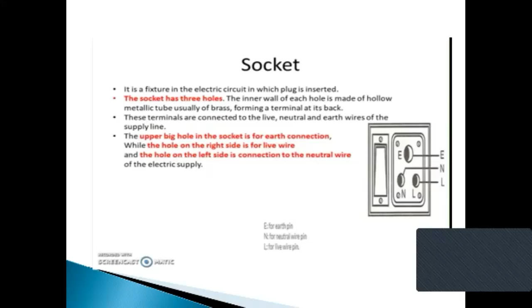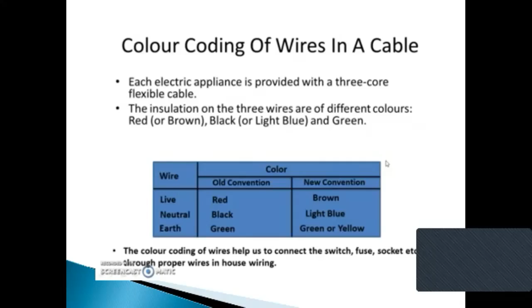Next one is color coding of wires in a cable. Earlier I have told you that the insulation on the three wires is of different colors: live is red, neutral is black, and earth is green. It is according to the old convention. According to the new convention, the live wire will be brown, the neutral wire will be light blue, and the earth wire will be green or yellow. The color coding of wires helps us to connect the switch, fuse, socket, etc. through the proper wire in house wiring, so that we understand this is live, this is neutral, and this is earth wire.